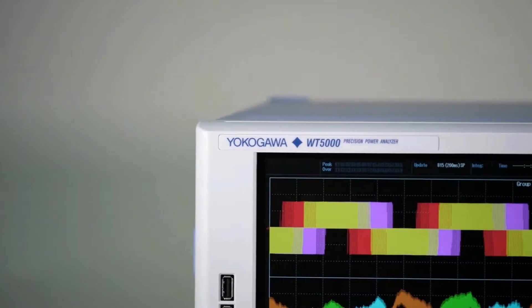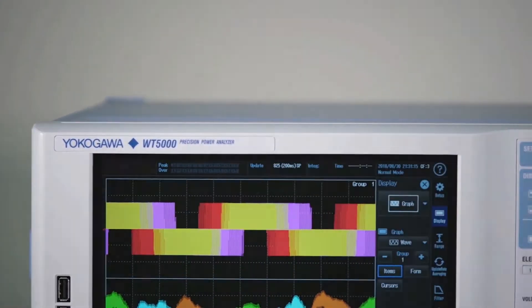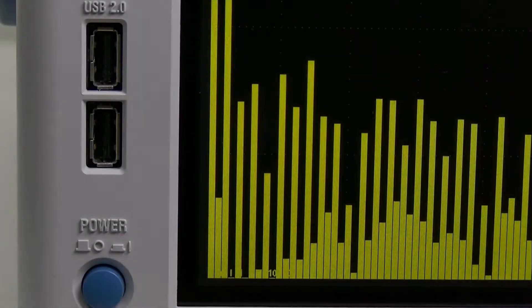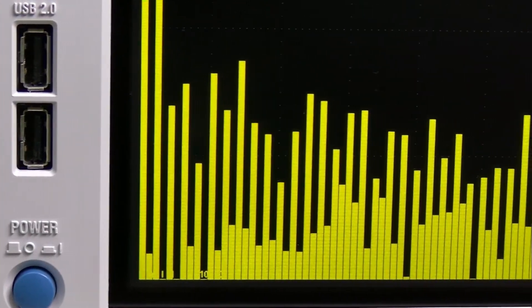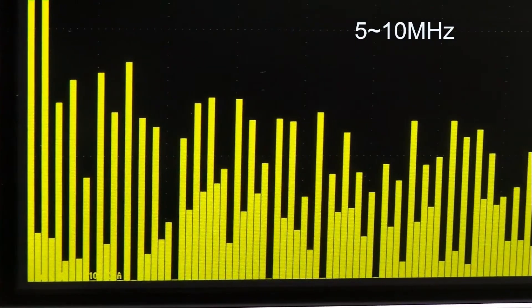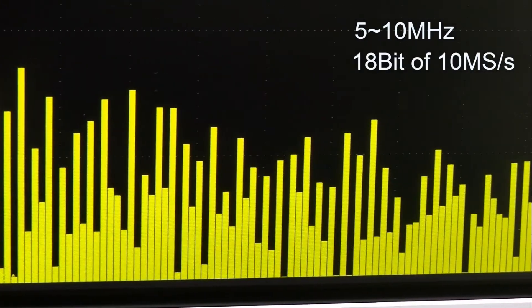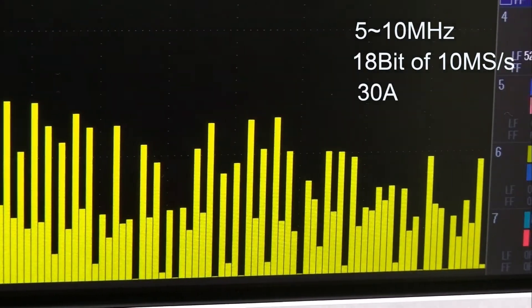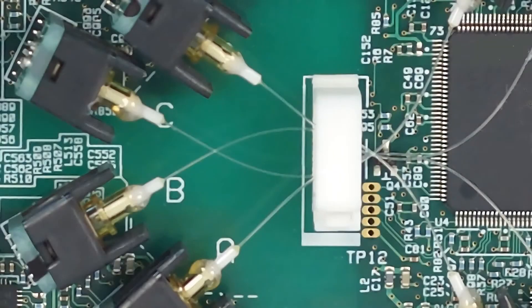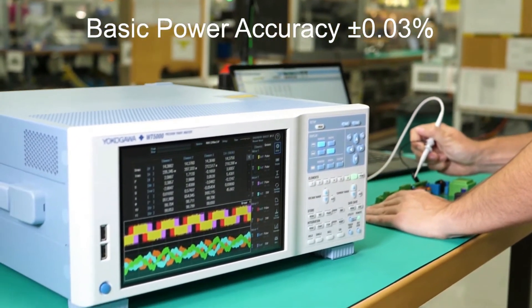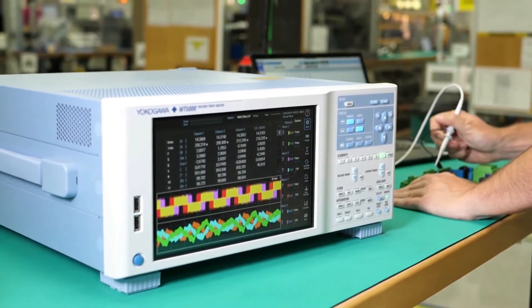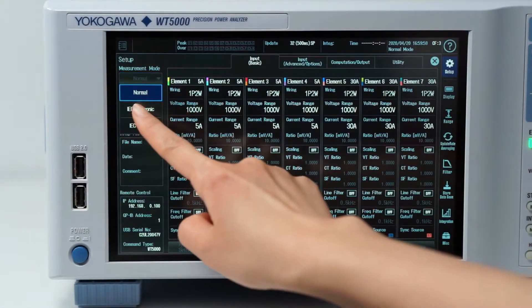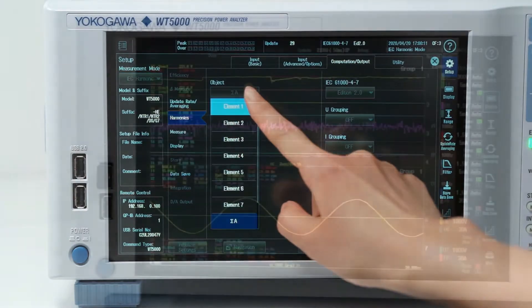Let's start by taking a look at the kinds of applications to which the WT5000 is particularly well suited. The Precision Power Analyzer has a frequency range of 5 up to 10 MHz, offers an 18-bit sampling rate of 10 mega samples per second and can measure a current of up to 30 amps. It has excellent isolation and noise immunity and its basic power accuracy is unmatched at ±0.03%. It complies with IEC standards for the testing of flicker and current harmonics.